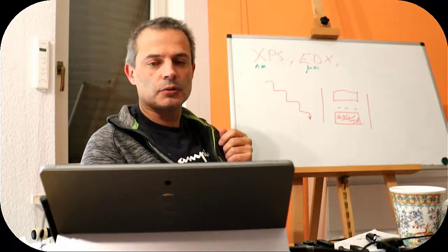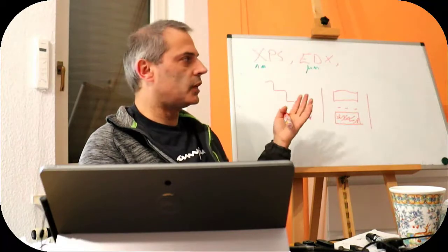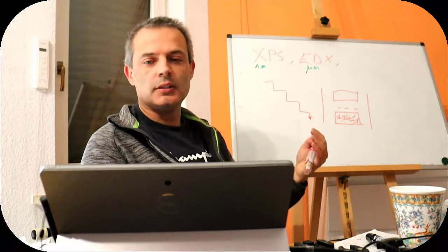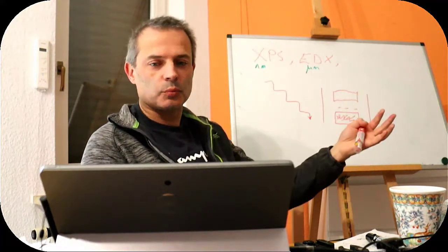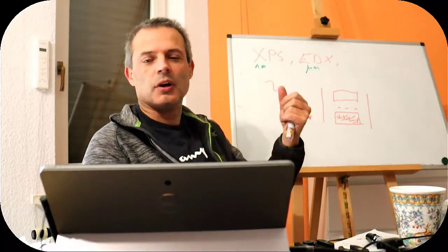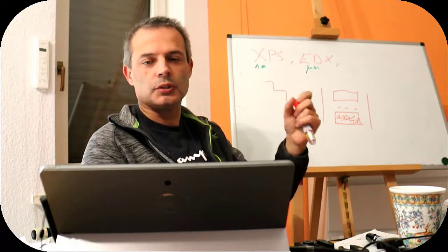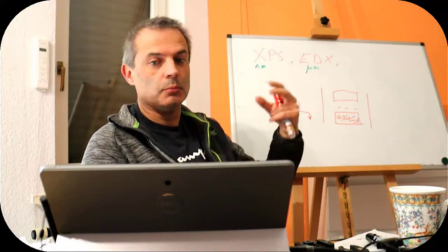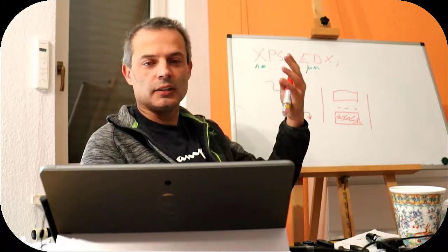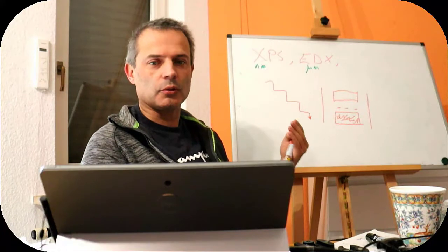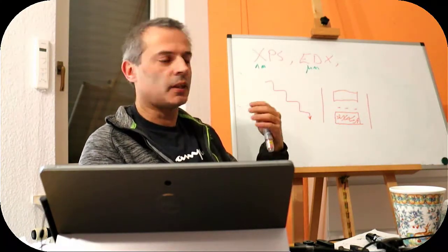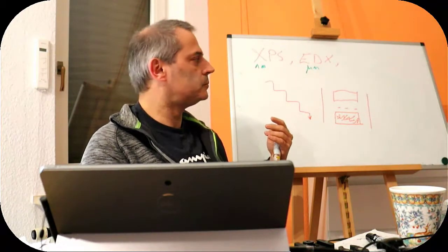There is another issue, of course, because of the constellation that we have. We've got an electron microscope, so we're measuring point for point and moving around the surface. We need to be able to collect as many X-rays as possible from each point without moving the camera, and that means we're only measuring effectively on one position on the camera. We can expand the beam to have a lot of surface that we're hitting with our beam, but we can't get a direct image, because that's not how scanning electron microscopy works. So we would be incompatible with the other system.